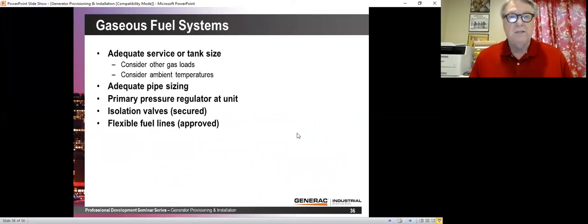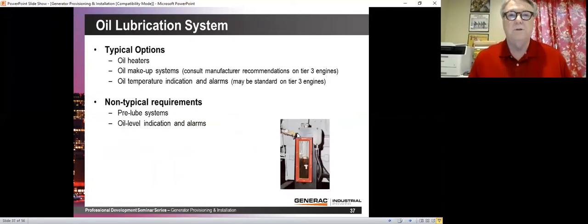There are some other things that we need to worry about. Isolation valves: I highly recommend that the isolation valves be padlockable in the open position so that somebody doesn't accidentally turn off the natural gas to your generator.